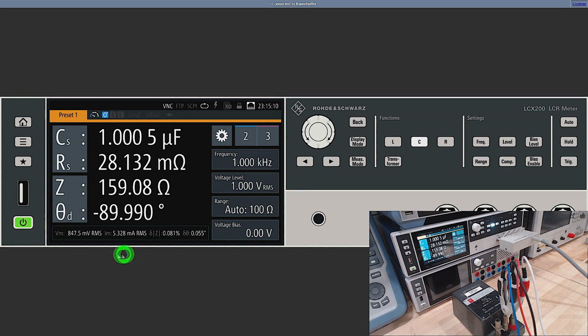Now, the other thing to look at is the actual measured voltage and current inside of the instrument. We're measuring 847 millivolts and about 5 milliamps, which puts us in a nice sweet spot in the measurement range of the unit. As a result, the confidence reported by the instrument on this measurement is pretty good, 0.081% for the impedance. So we can rely on this measurement.